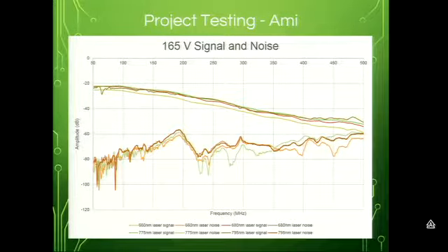So this is a sample of something that we would get out of the network analyzer. The top is the signal and the bottom is the noise. So you can see the signal-to-noise ratio, it's in dB, so the amplitude is in dB, it's a Bode plot, and the frequency is the modulation frequency, it's not the frequency of light. And it goes from 50 to 500 megahertz, and you can see that the signal is pretty far from the noise until about 450, and it starts getting pretty close, and it wouldn't be as readable around there.